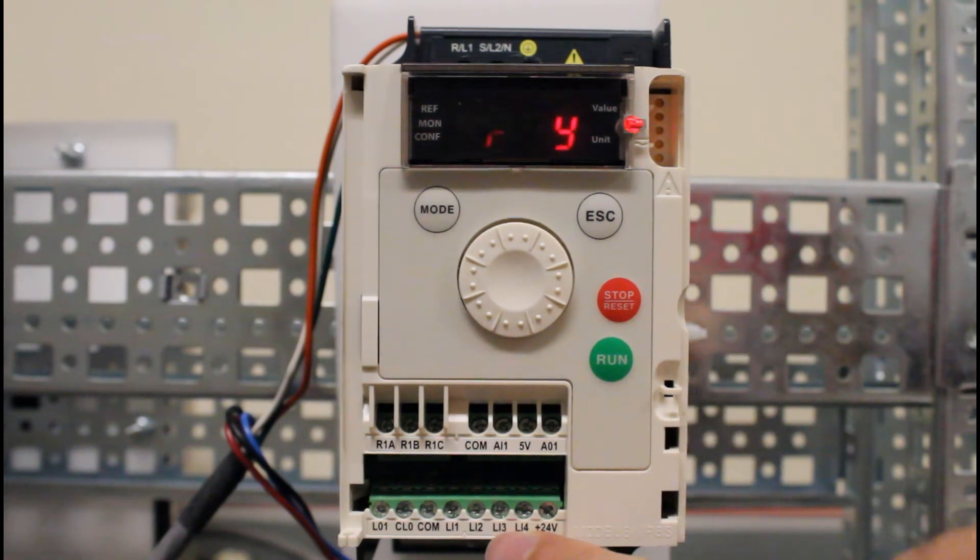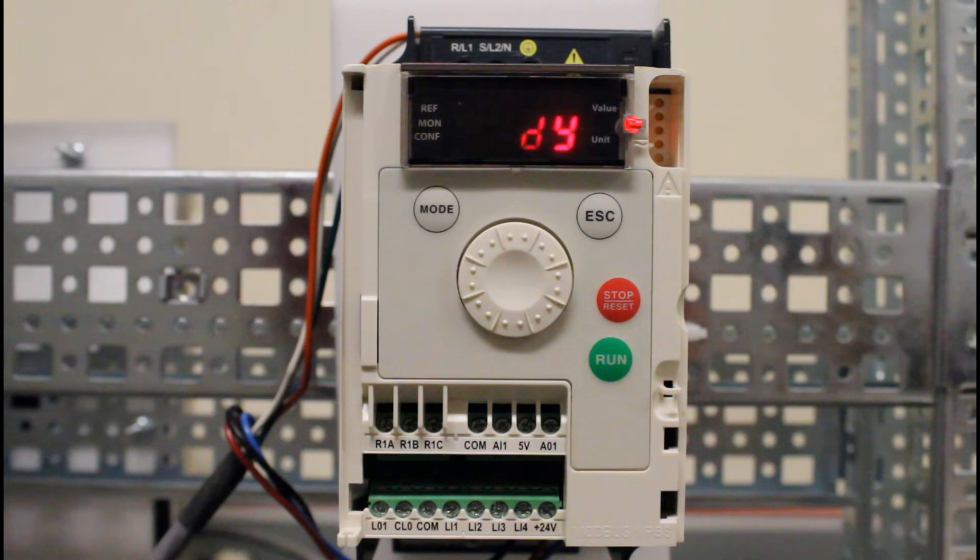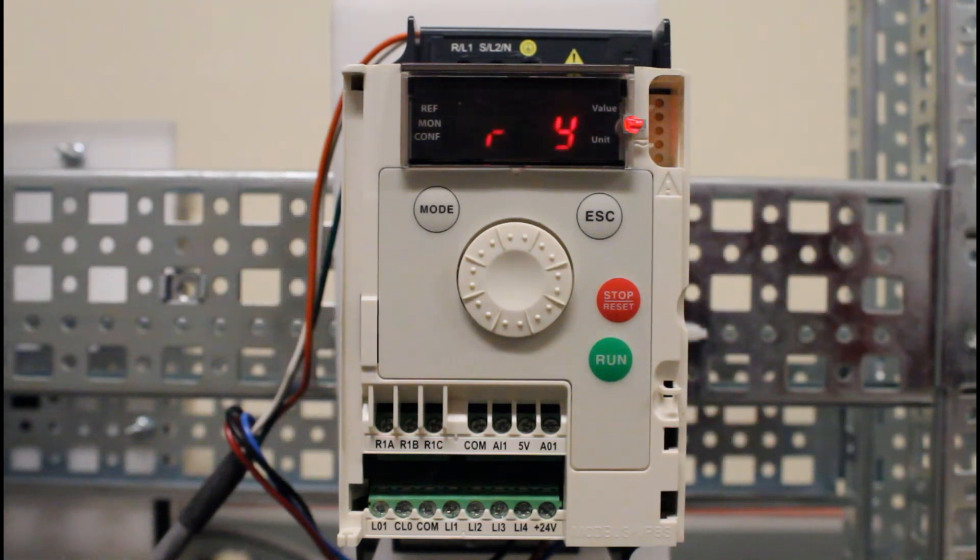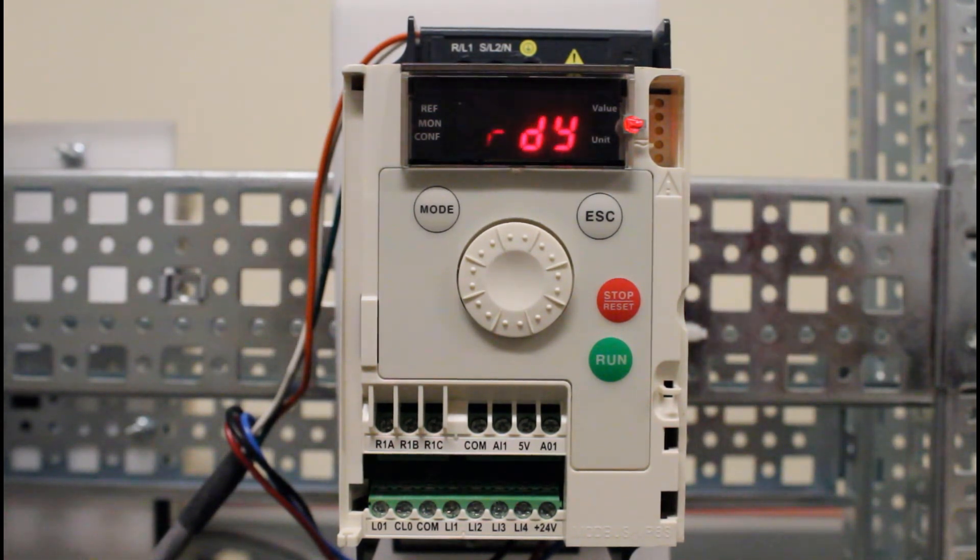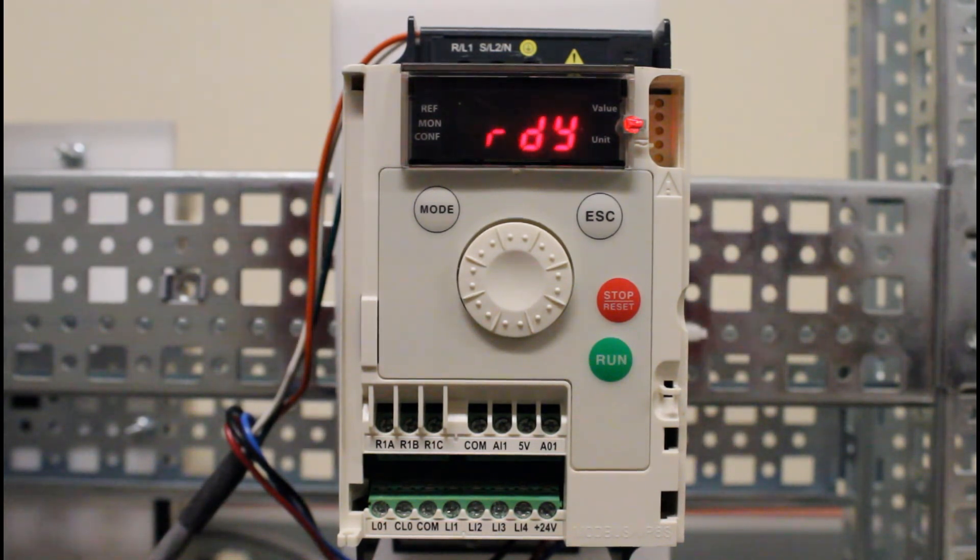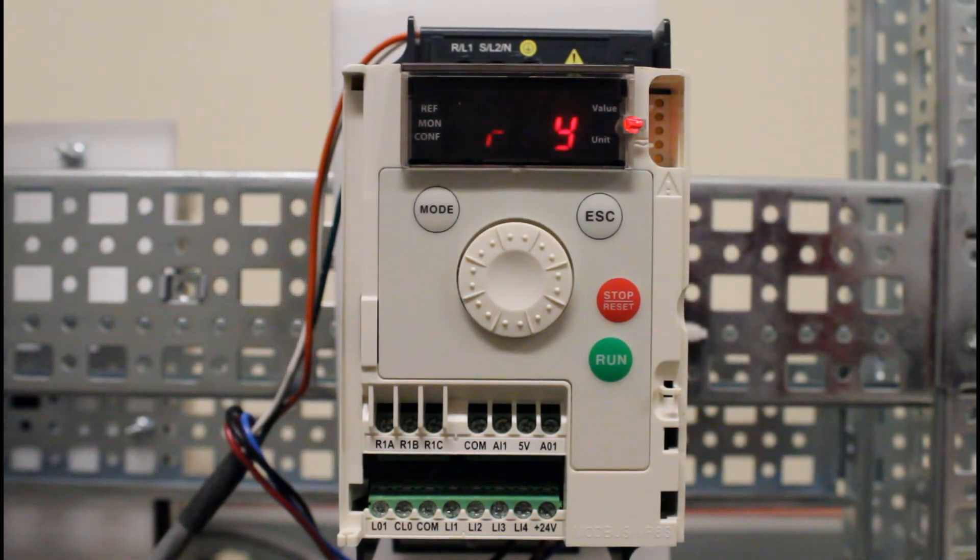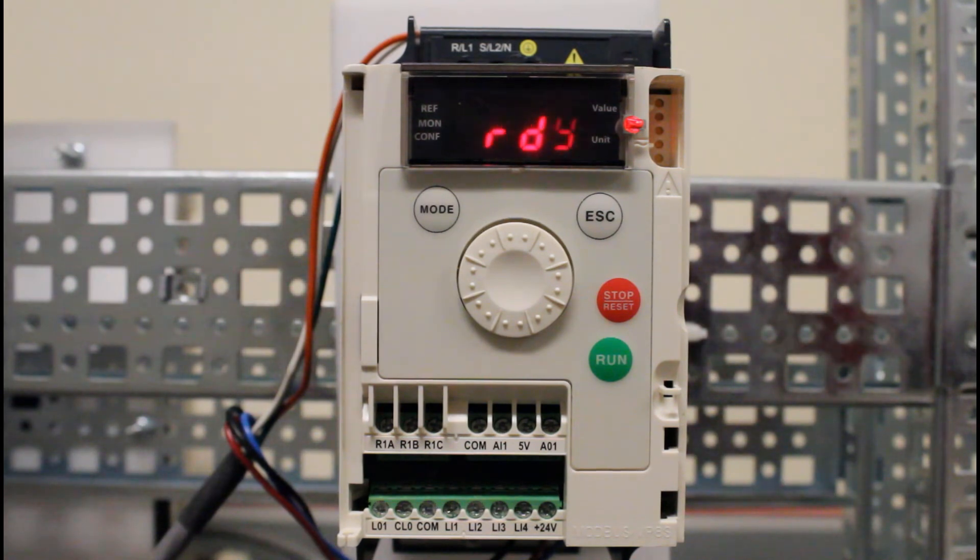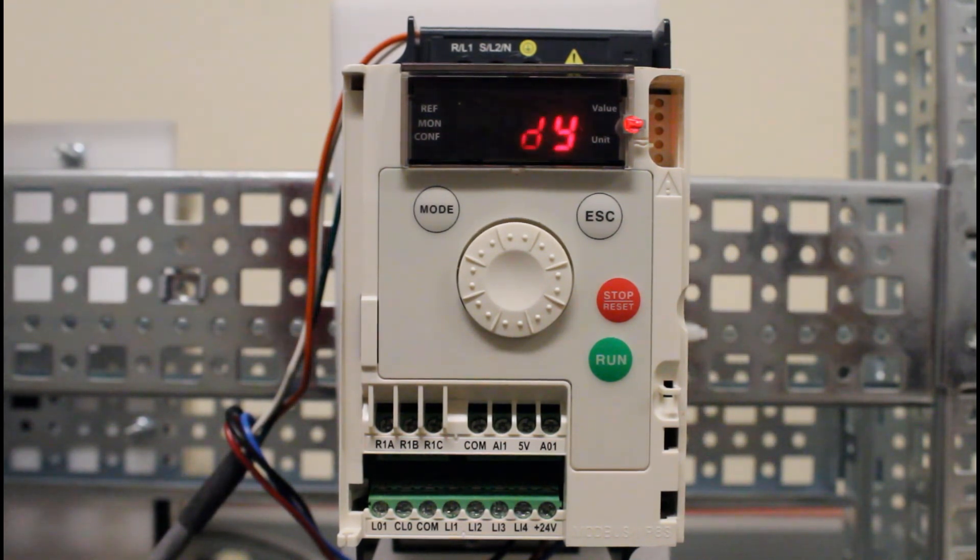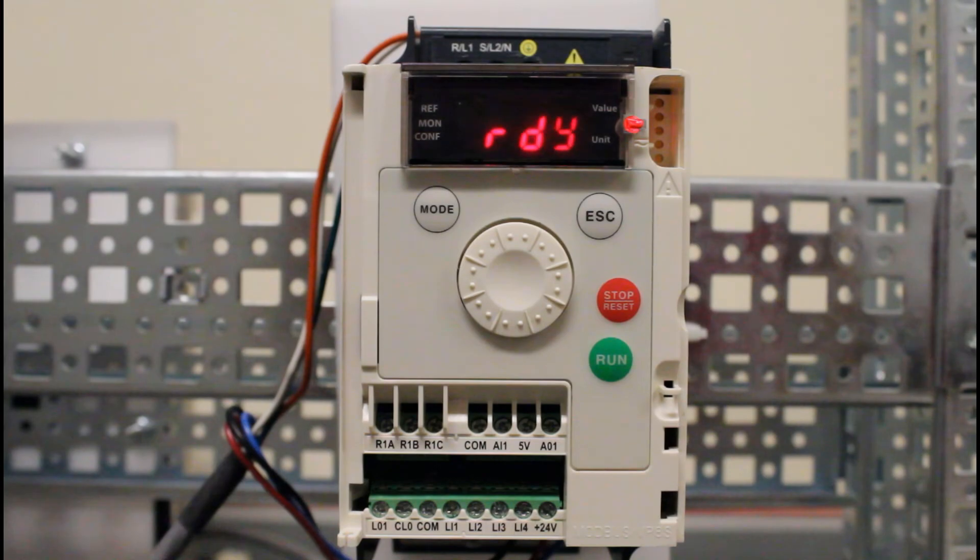Next time you give it a run command and you lose power, when the power comes back up on its own, as long as your run command is there it should go ahead and take off and run for you without having to come in front of it to power down or give it a run command again. This is how you set up the ATV12 drive for automatic restart function.